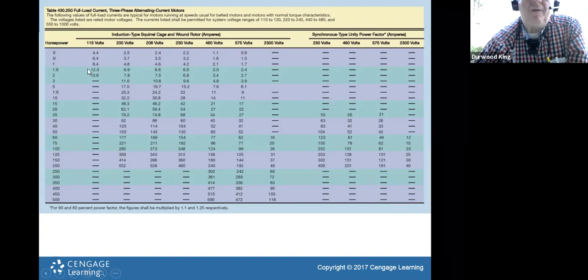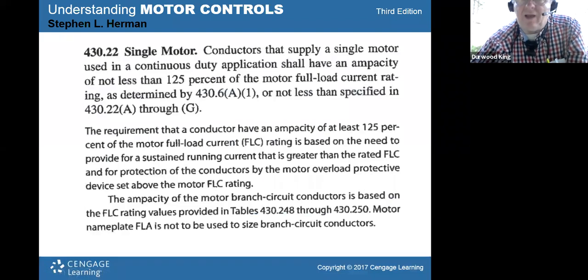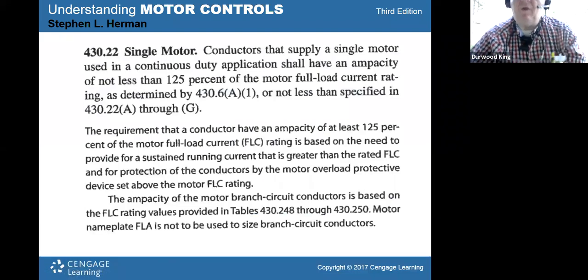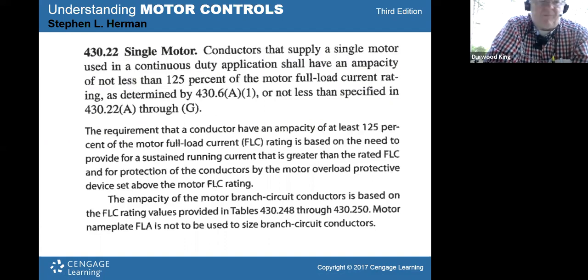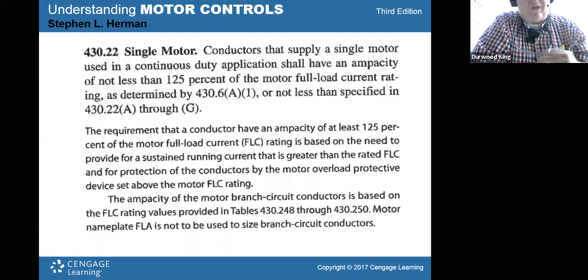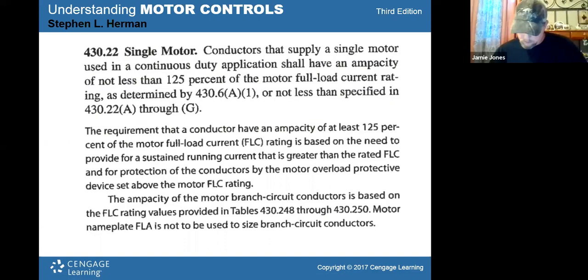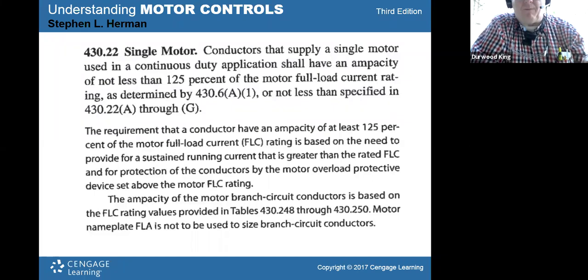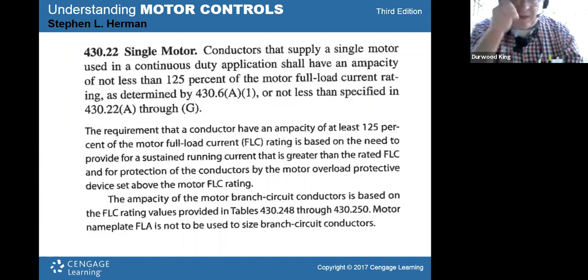Now, this is where you get the amp rating for the motor, like we just saw. This is how you calculate the amps so that you can pick the right size wire. So basically it's this, guys. Just remember 125%. Whatever the amp rating of the motor is, if it's 10 amps, you want to multiply that 10 amps times 125%, which would be 1.25. So what's 10 amps times 1.25? 12 and a half. So that's the actual amp rating that you've got to size the wire by. When you pick a wire size, it's got to be based on 12.5 amps, not on 10 amps. Okay? So that's the first thing.